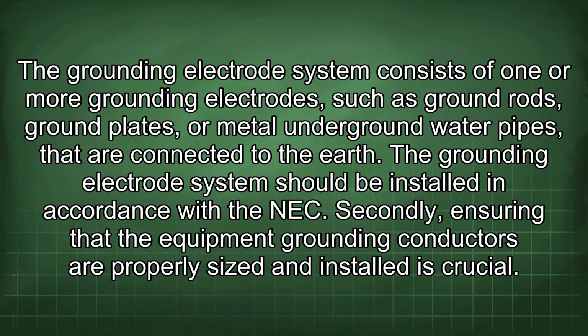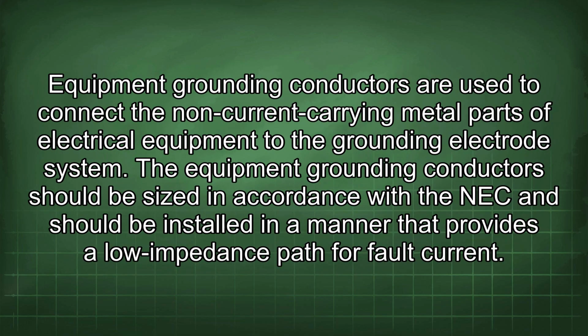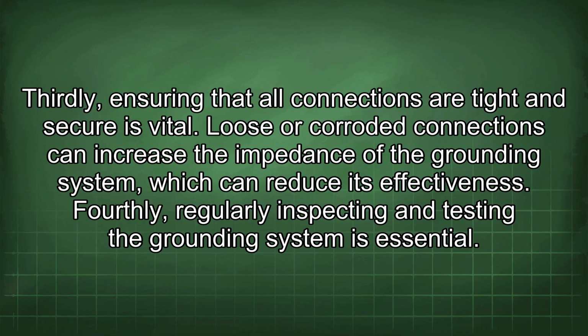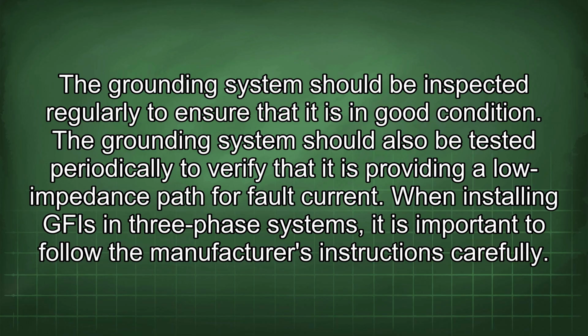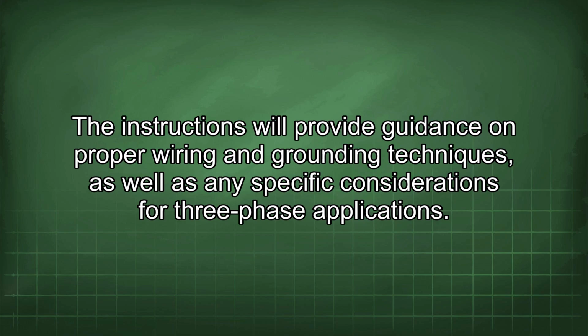Secondly, ensuring that the equipment grounding conductors are properly sized and installed is crucial. Equipment grounding conductors are used to connect the non-current carrying metal parts of electrical equipment to the grounding electrode system. The equipment grounding conductors should be sized in accordance with the NEC and should be installed in a manner that provides a low impedance path for fault current. Thirdly, ensuring that all connections are tight and secure is vital. Loose or corroded connections can increase the impedance of the grounding system, which can reduce its effectiveness. Fourthly, regularly inspecting and testing the grounding system is essential. The grounding system should be inspected regularly to ensure that it is in good condition. The grounding system should also be tested periodically to verify that it is providing a low impedance path for fault current. When installing GFI in three-phase systems, it is important to follow the manufacturer's instructions carefully. The instructions will provide guidance on proper wiring and grounding techniques, as well as any specific considerations for three-phase applications.